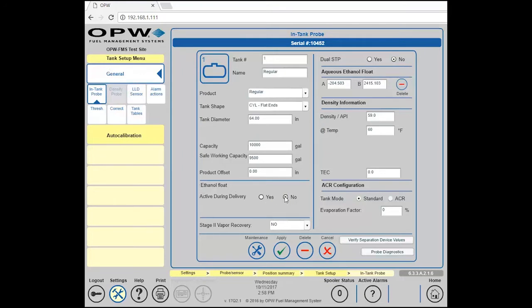We would normally leave this set to no, so we would not be looking for a separation while we were getting a delivery. The turbulence in the tank can oftentimes move our sensor enough to cause an alarm. But we also have two new fields up here that are already populated for the aqueous ethanol float. And if you'll notice, we have our A and B level. These are the numbers that we recorded off of the sticker that came with the float kit itself. Or if you lost that sticker, these numbers are recorded on the float itself. They're stamped into the Nitrophyl. So these would normally default to zeros, and you would have to put in the A and the B levels and then apply.